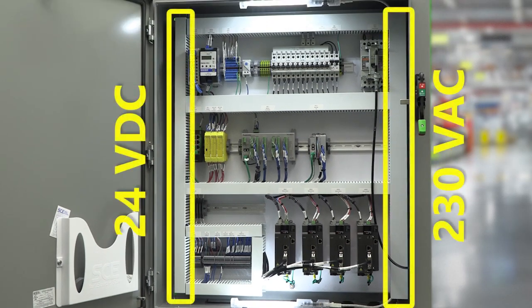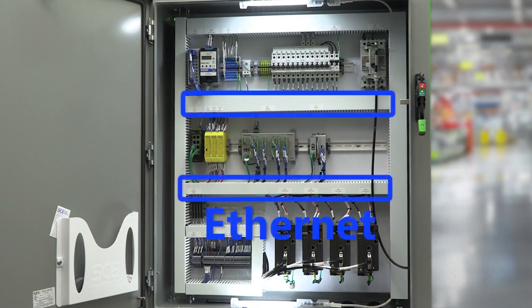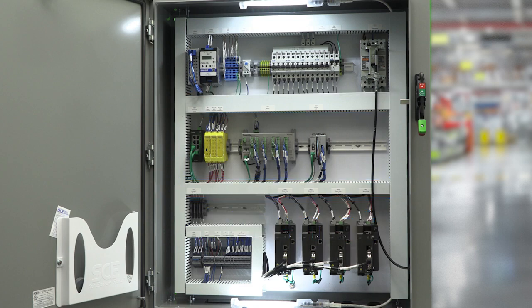24-volt DC power and signals stay to the left. Areas where 3-phase power and low-voltage DC power have to get close to each other are separated by wire duct dividers. Ethernet cables get their own bundle, but can share space in the wire duct with 24-volt wiring. Keeping with the theme of a bottom exit for cables, the PLC's I/O terminal blocks are placed at the bottom left of the panel. Additionally, components are spaced away from wire duct and other devices based on their installation manuals.